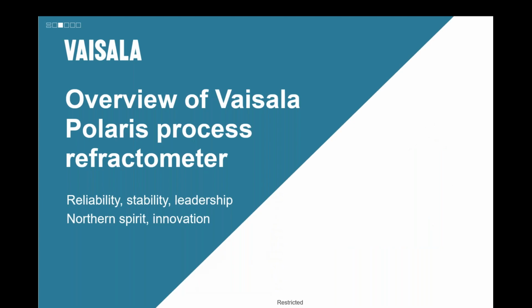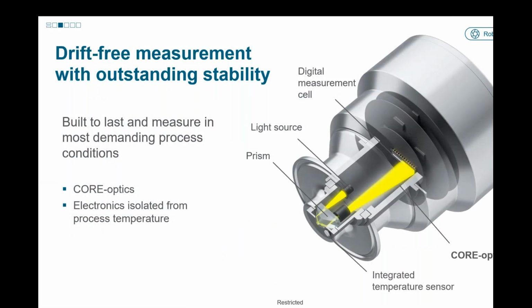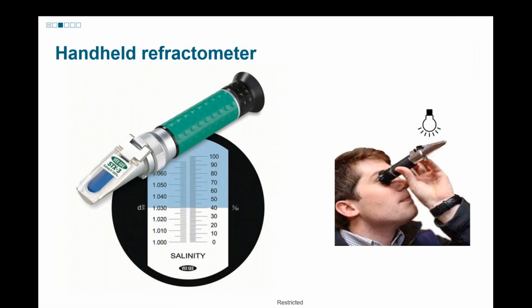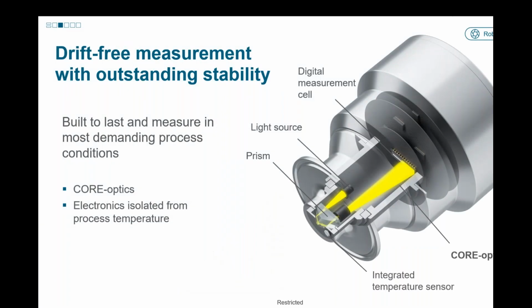So now we'll get into the overview of our refractometer. So we have what we call the core optics. The core optics is a light source, a very specific wavelength of light or color of light that shines from within the core optics, strikes the prism, and then it bounces around in that prism and comes back to a CCD or detector that looks at the shadow line that we saw on the previous slide. It actually creates a shadow much like this one here, and we look at where that lands. That's what we call the critical angle. So some of the light from this light source gets refracted into the process, while some of the light gets reflected back. And that critical angle creates that shadow, and that's what we are measuring.